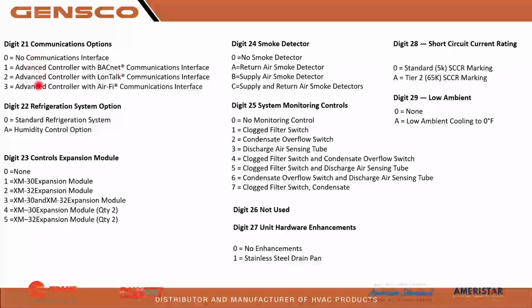Digit 21, you're going to order it with it already in there. It's going to come from factory ready to talk to your building automation system with some addressing. I haven't seen any with the expansion module. Here's our digit 24 smoke detector. You can order it with the supply smoke too. And you're going to also have another board, that customer connections. That supply smoke fits into another board, so you'll have an accessory on there. And if it's not ordered from factory, you'll see a 0, no smoke detector.